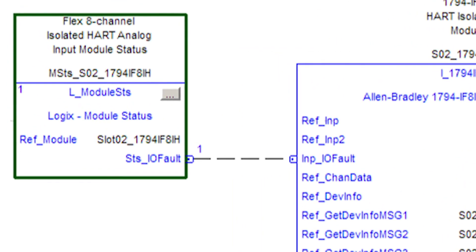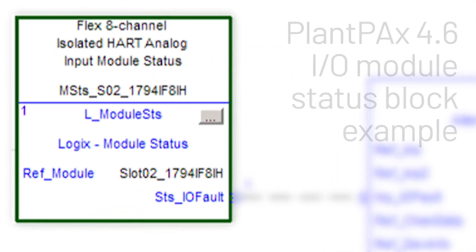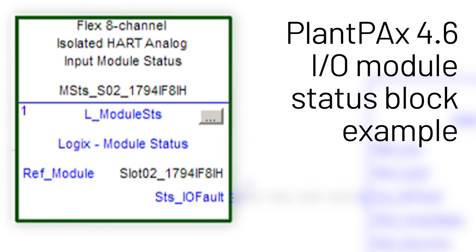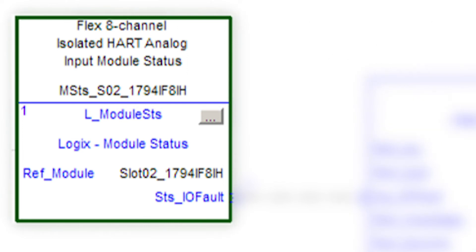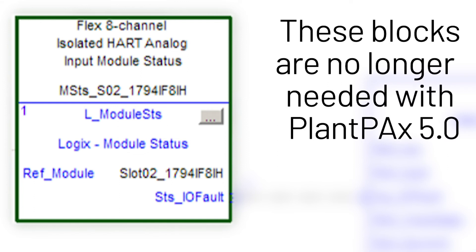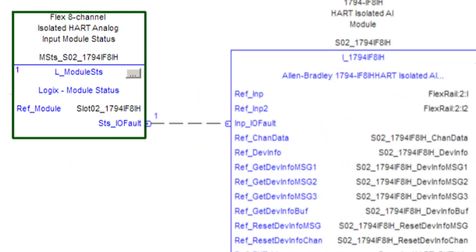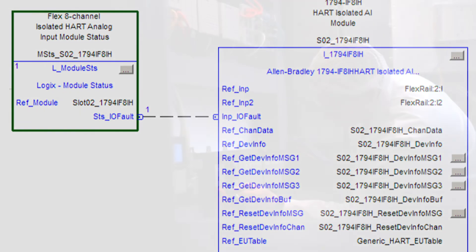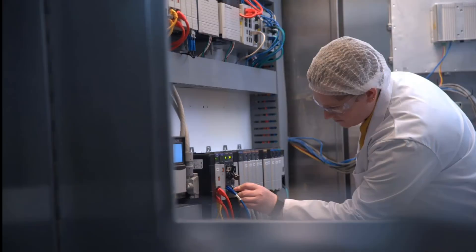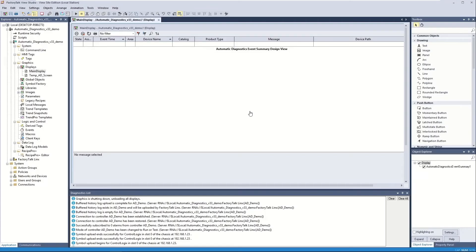With PlantPAX 4.6, hardware alarms like the IO module status blocks from Rockwell Automation Library of Logix Diagnostic Objects 4.1 needed to be configured in the controller to monitor IO faults. With PlantPAX 5.0, just plugging in the module in the rack automatically enables the hardware alarms and automatically logs the events in your SQL database.